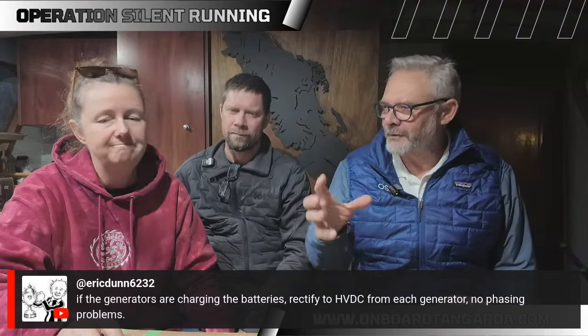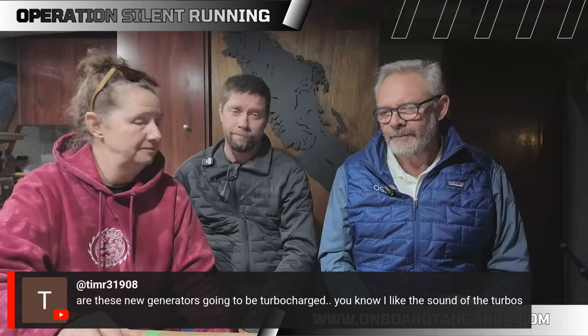Eric says if the generators are charging the batteries, you can rectify to HVDC from each generator with no phasing problems. Right, that's what we resulted in. If we go with AC generators, that's exactly what we're going to do. Are these new generators going to be turbocharged? I like the sound of turbos. They likely will, most of the ones we're looking at are, because that's a good way to get bonus efficiency.